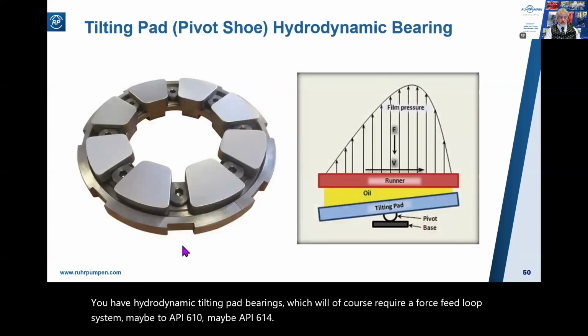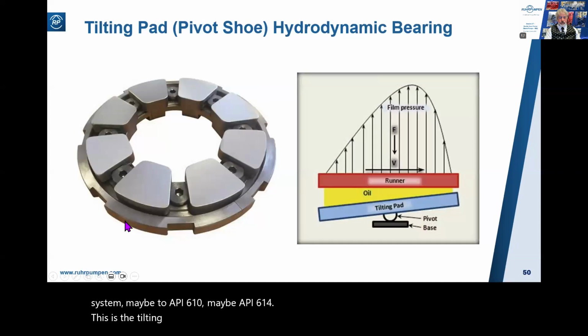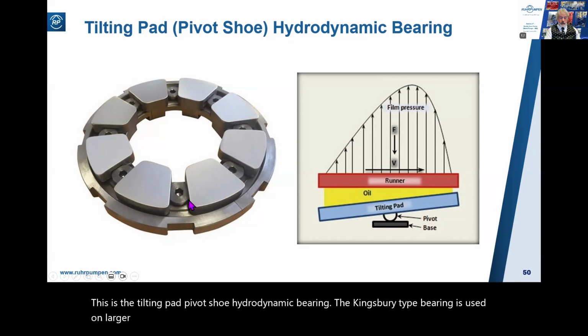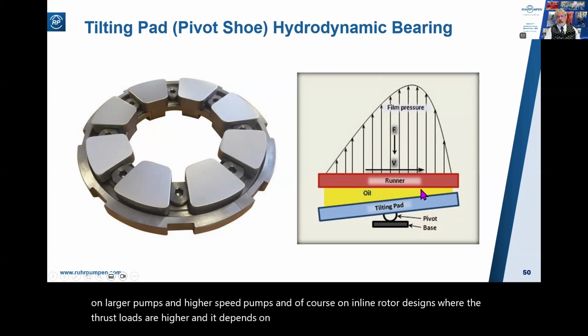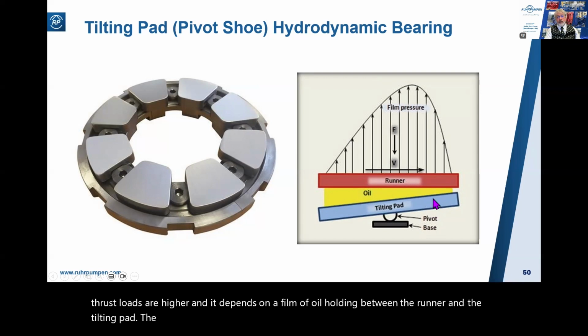This is the tilting pad pivot shoe hydrodynamic bearing, the Kingsbury type bearing. It's used on larger pumps and higher speed pumps, and of course on inline rotor designs where the thrust loads are higher. And it depends on a film of oil holding between the runner and the tilting pad. The tilting pad tilts, pivots to maintain this oil film.